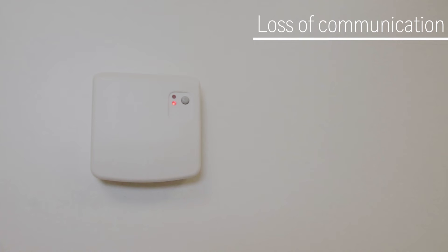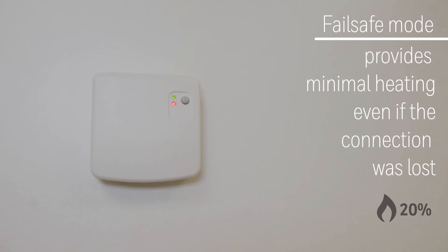If the unit has lost communications from all the controllers it is bound with, the red light will be on continuously. If the green light turns on during the loss of communication, the relay has entered fail-safe mode and controls at 20% heating demand.